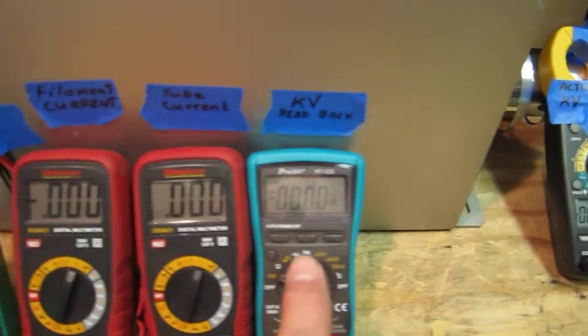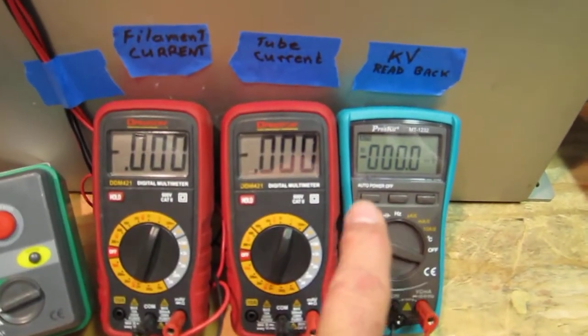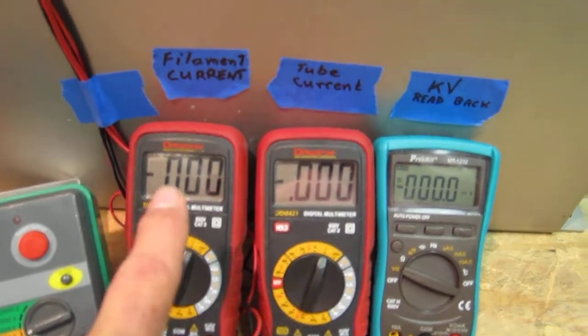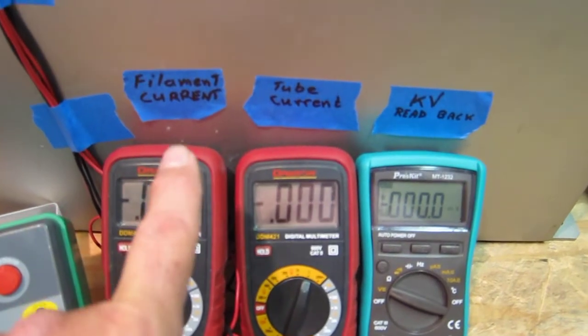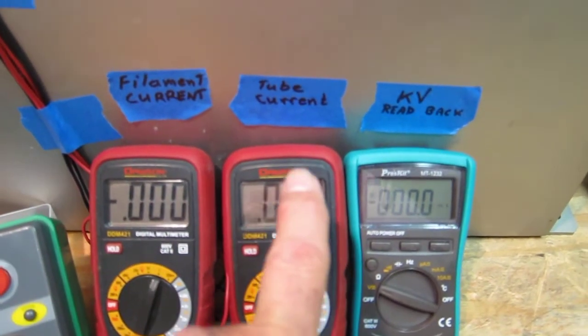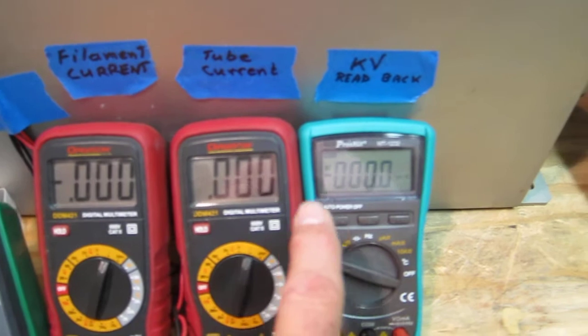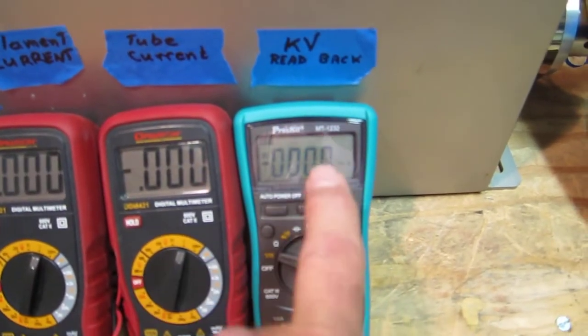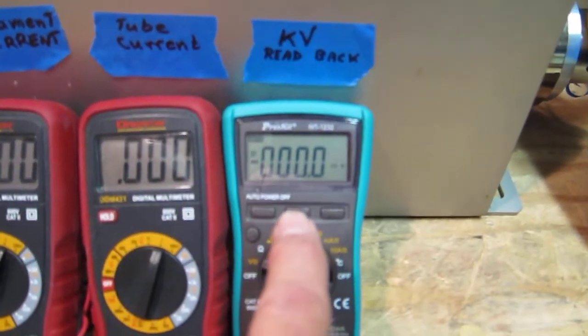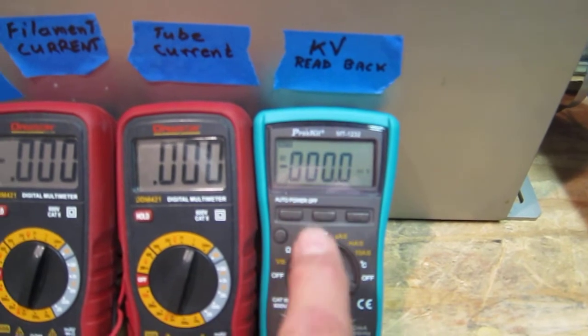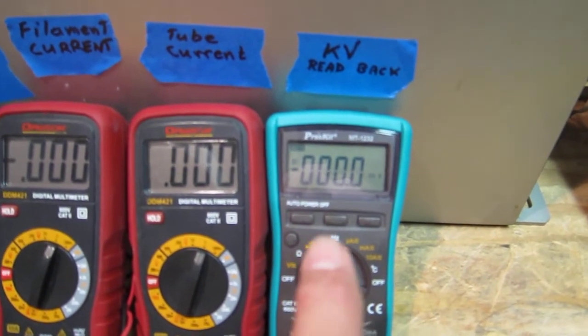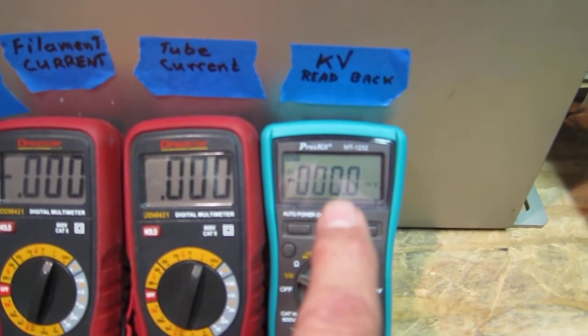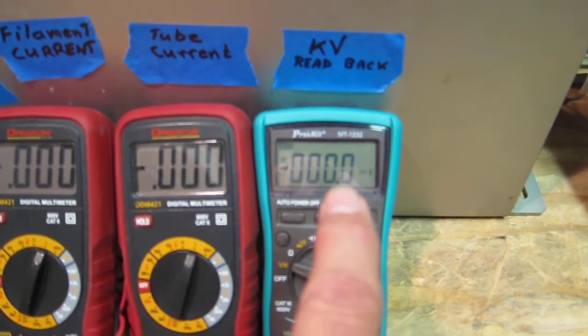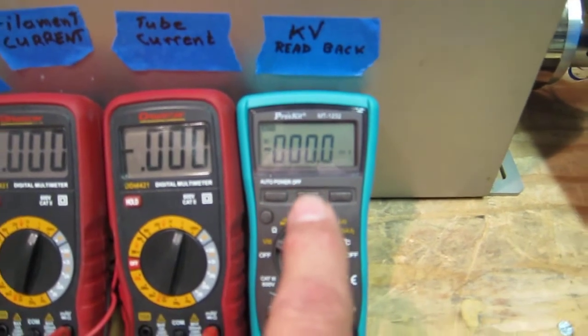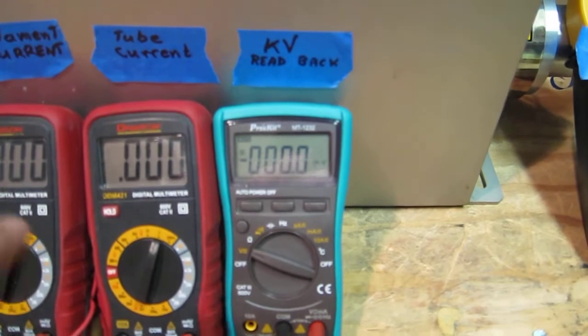These 3 meters would be analog inputs to the computer system on the X-ray machine. Here would be the filament current, the tube current, and over here the kilovoltage readback that would go also to the front panel. And of course it's going to be scaled. I believe it will be 0 to 10 volts, or it may be 0 to 12 volts.